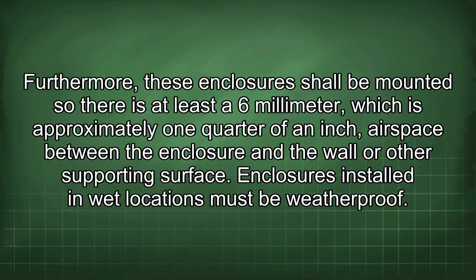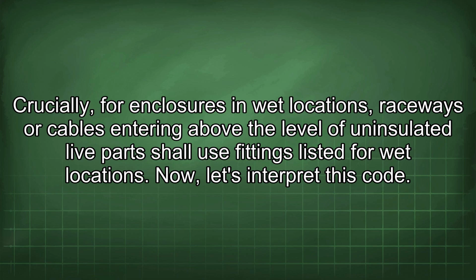Enclosures installed in wet locations must be weatherproof. Crucially, for enclosures in wet locations, raceways or cables entering above the level of uninsulated live parts shall use fittings listed for wet locations. Now let's interpret this code.